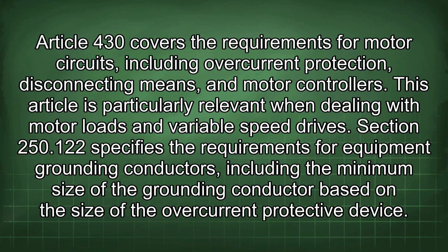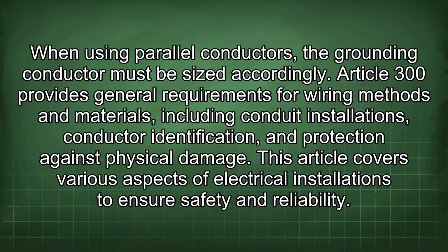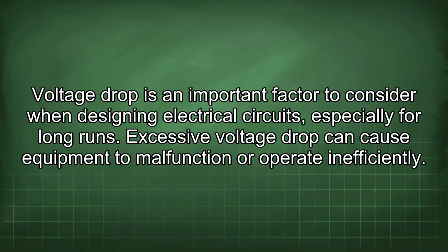Article 430 covers the requirements for motor circuits, including overcurrent protection, disconnecting means, and motor controllers. This article is particularly relevant when dealing with motor loads and variable speed drives. Section 250.122 specifies the requirements for equipment grounding conductors, including the minimum size of the grounding conductor based on the size of the overcurrent protective device. When using parallel conductors, the grounding conductor must be sized accordingly. Article 300 provides general requirements for wiring methods and materials, including conduit installations, conductor identification, and protection against physical damage. This article covers various aspects of electrical installations to ensure safety and reliability. Voltage drop is an important factor to consider when designing electrical circuits, especially for long runs. Excessive voltage drop can cause equipment to malfunction or operate inefficiently.